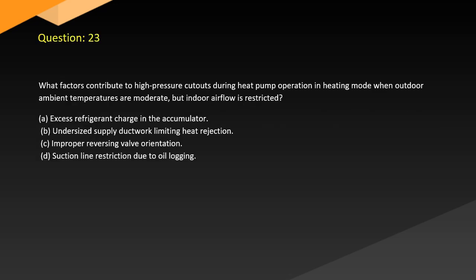Question 23. What factors contribute to high-pressure cutouts during heat pump operation in heating mode when outdoor ambient temperatures are moderate, but indoor airflow is restricted? A. Excess refrigerant charge in the accumulator. B. Undersized supply ductwork limiting heat rejection. C. Improper reversing valve orientation. D. Suction line restriction due to oil logging.